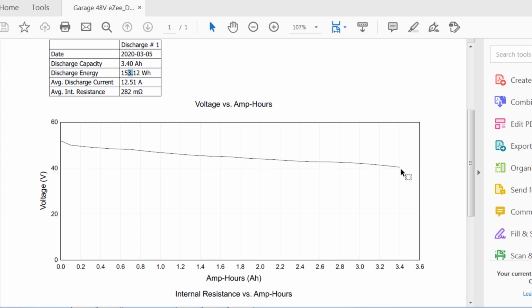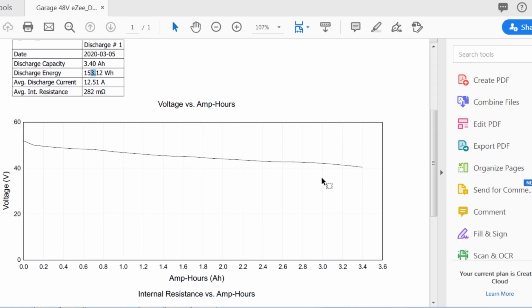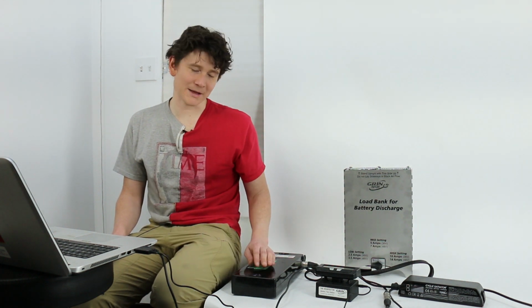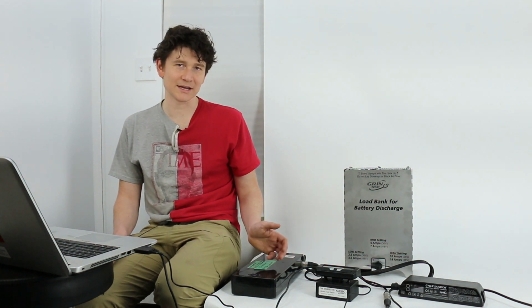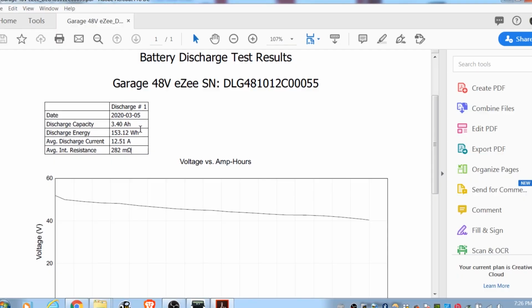So we know it's not just one cell that was bad, but the entire pack showing low capacity. If we'd seen the voltage sitting at maybe 48 or 46 volts when the BMS shut off, it might be worth opening the pack to identify a single cell group responsible. But here we just have a battery that's really end of life, which we can also tell from the average internal resistance data, close to 300 milliohms, whereas when this pack was new, internal resistance was more like 150 to 180 milliohms.